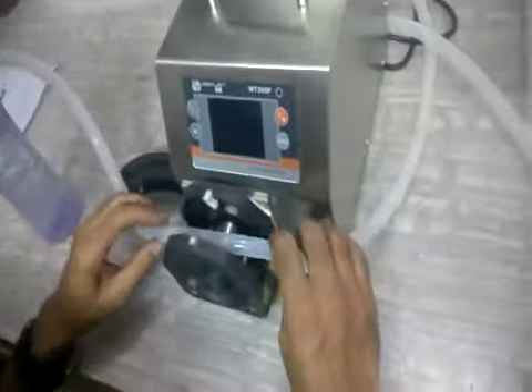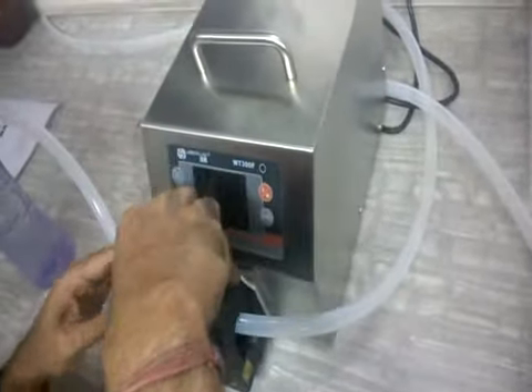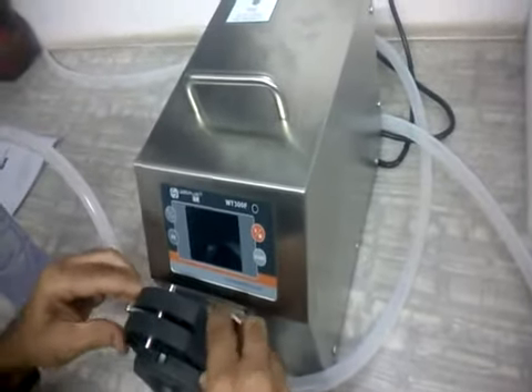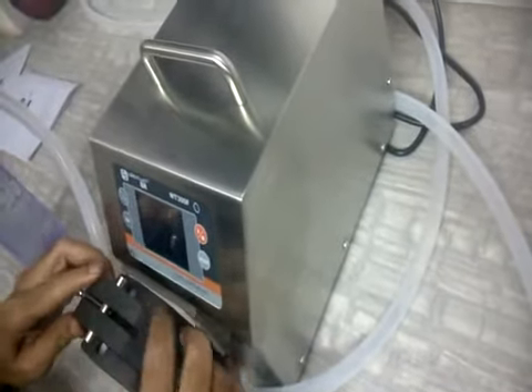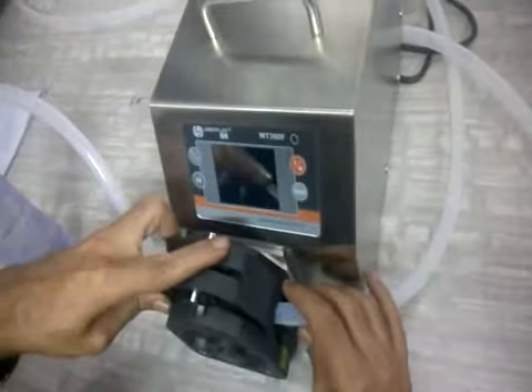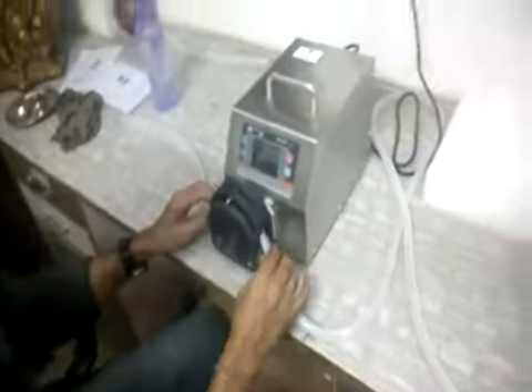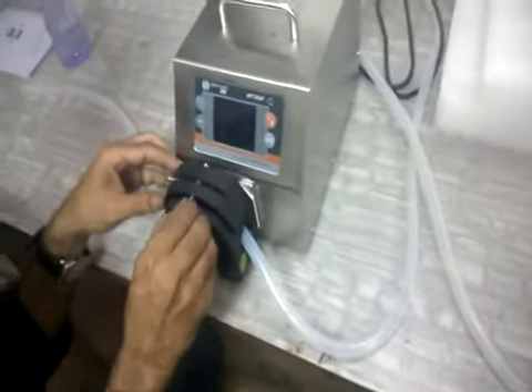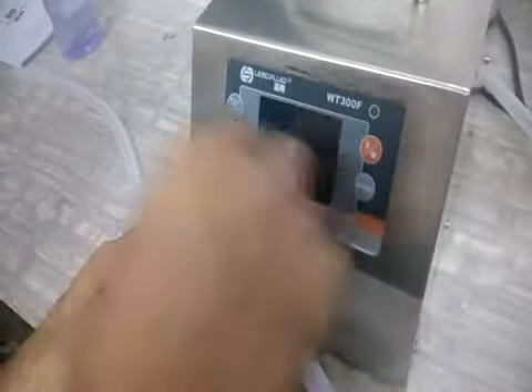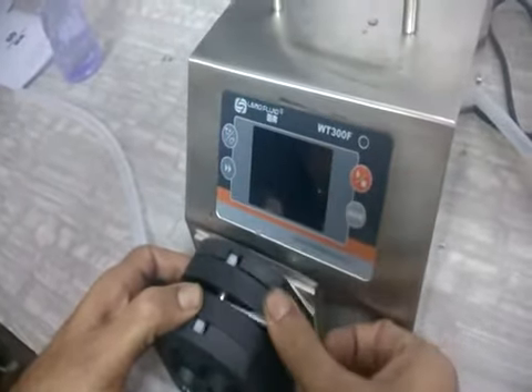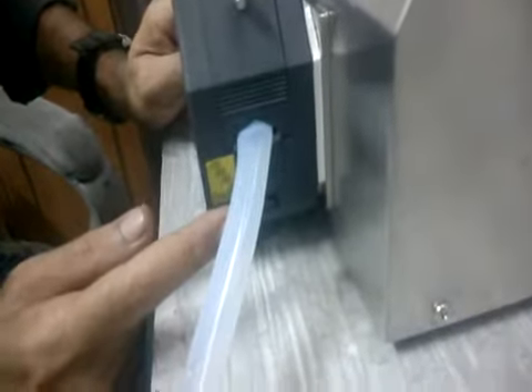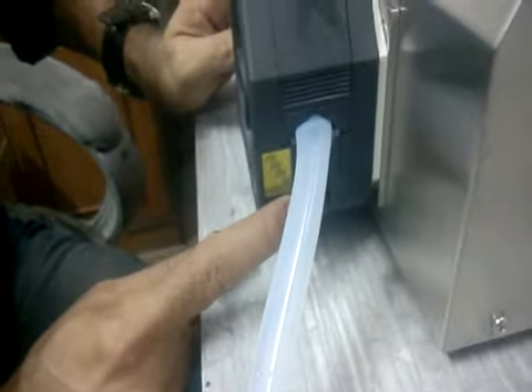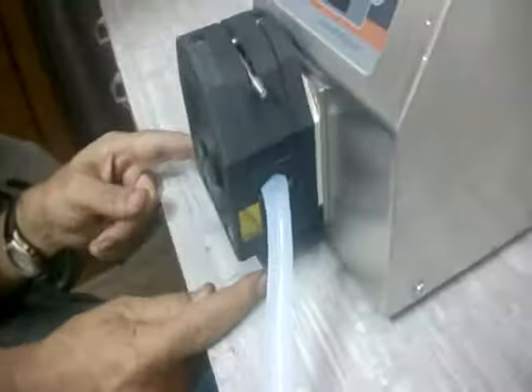Just put the tube and from the top just press this, and maybe you will have to align this notch here. So we have loaded the tubing. Just align this notch in this gap and press it down. Once it is pressed down, move this lever to the other side and the tubing gets locked. Make sure, like we have loaded the 36 number tubing, the distance of this is as per the 36 number.